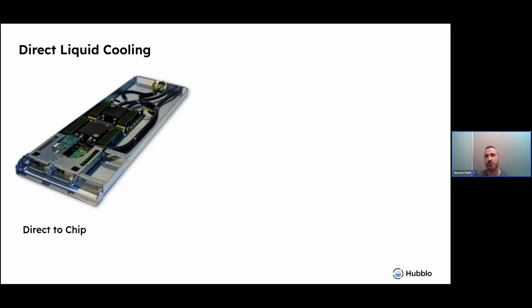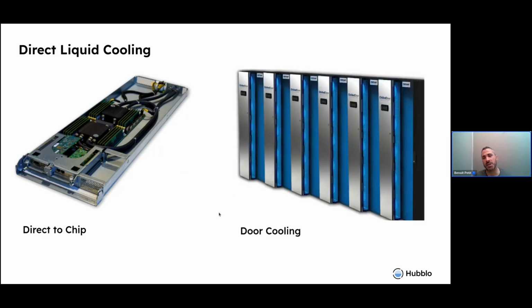To distinguish between door cooling and direct liquid to chip cooling, direct to chip might look like this. You will have pipes inside the server that will get the liquids up to a surface that's directly on the chip. And regarding door cooling, it will be just special racks with doors that are connected to the liquid circuit. But then it will be air that will be sent to the servers themselves and not liquid pipes.